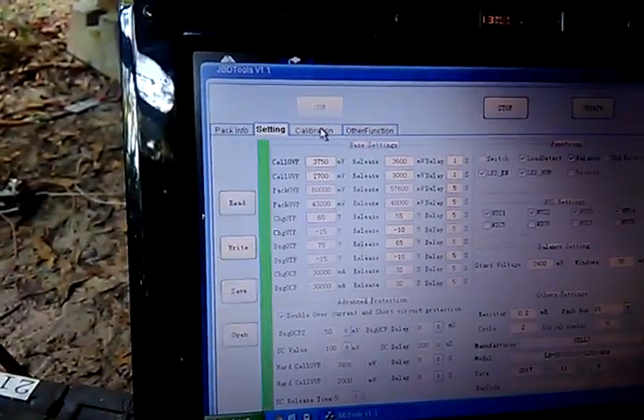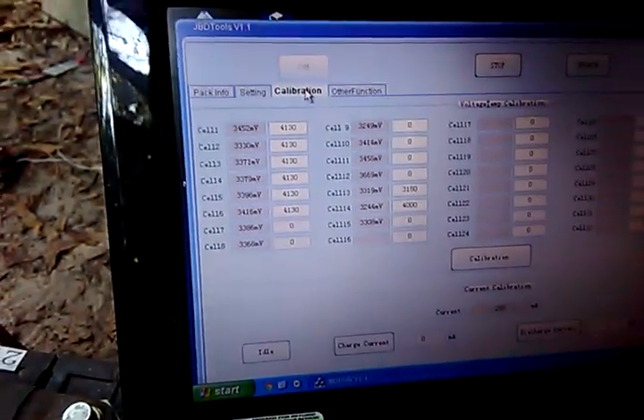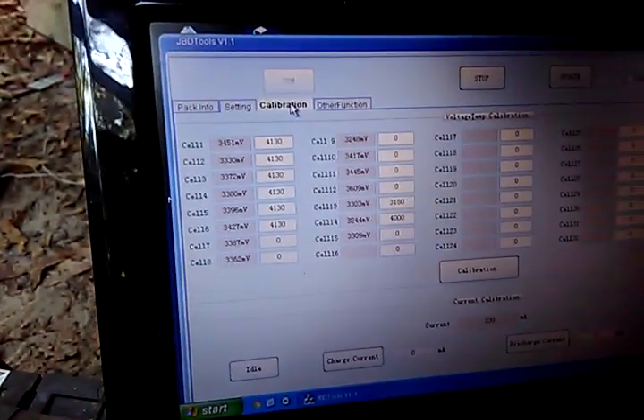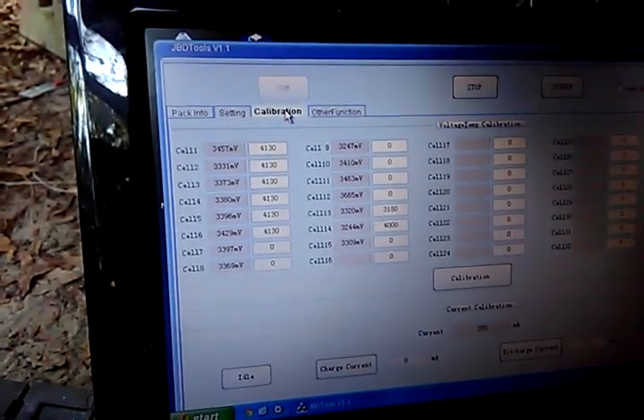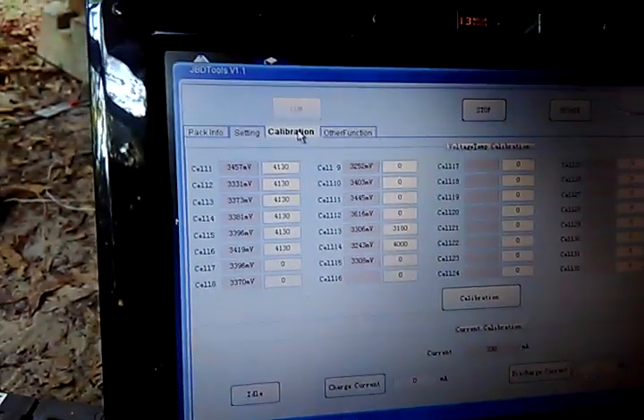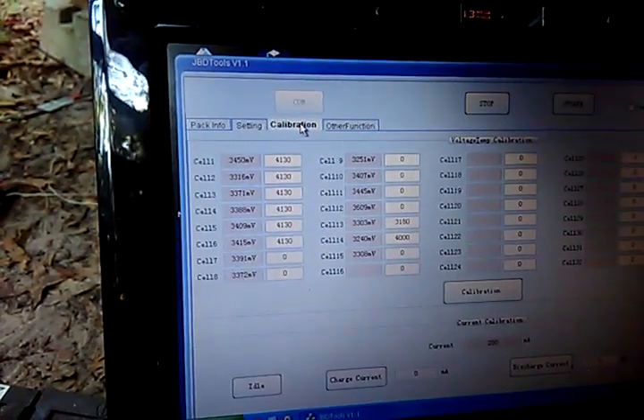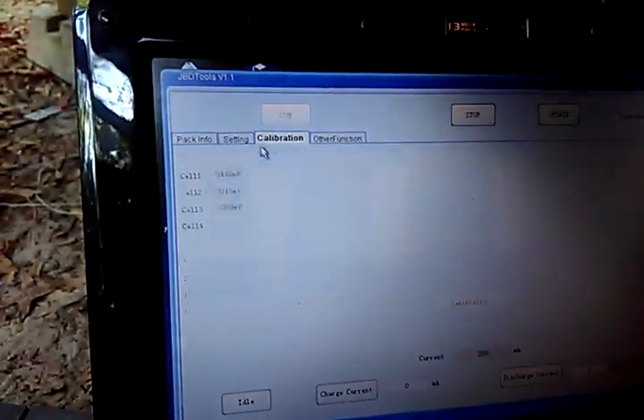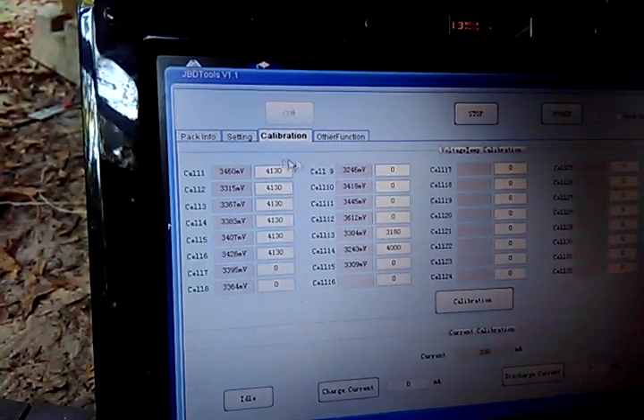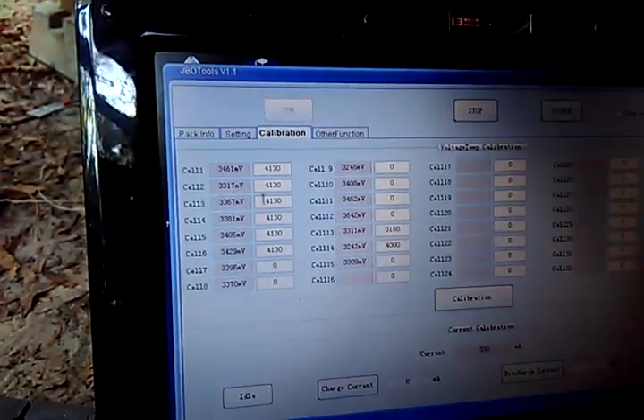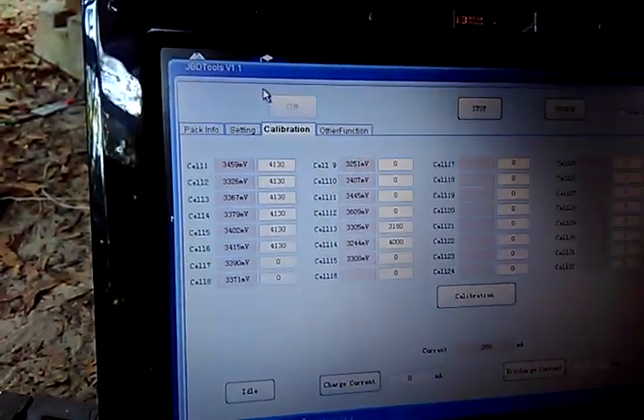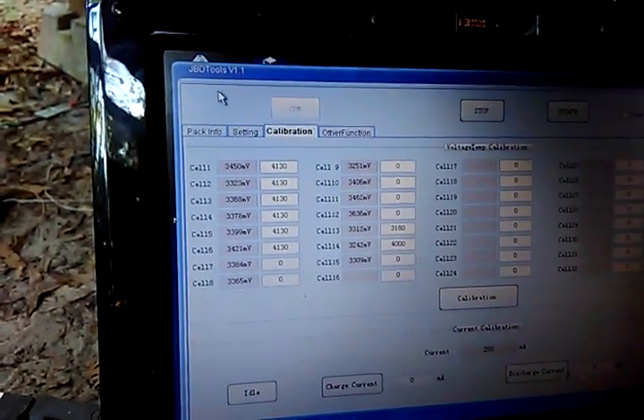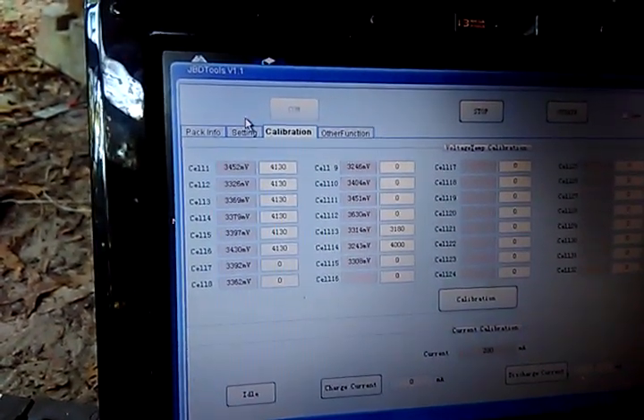The other thing we've got is a calibration thing here, so you can actually calibrate all these, and you really need to because your wires will be different lengths and there's a lot of things that can throw that off. So we take a good meter, we read our voltage, we type it into there, and after we've done everybody we hit the calibrate and it rearranges things to the voltage that we have it set for.